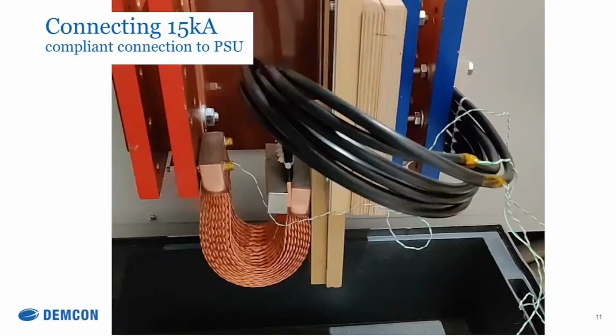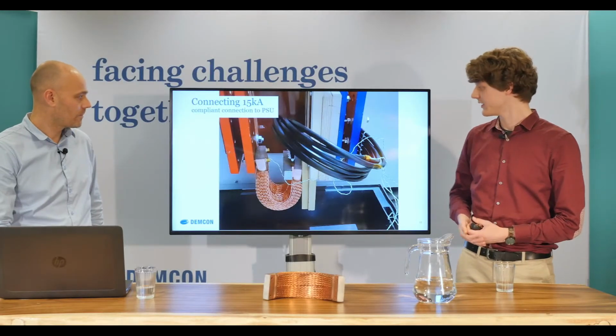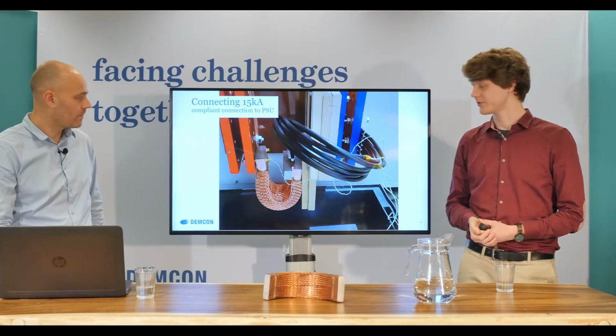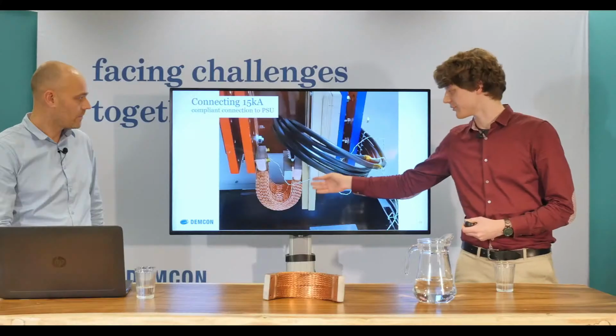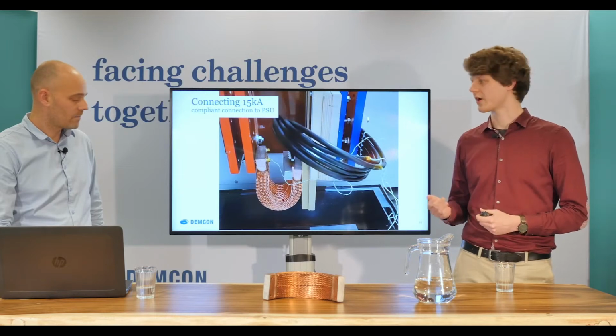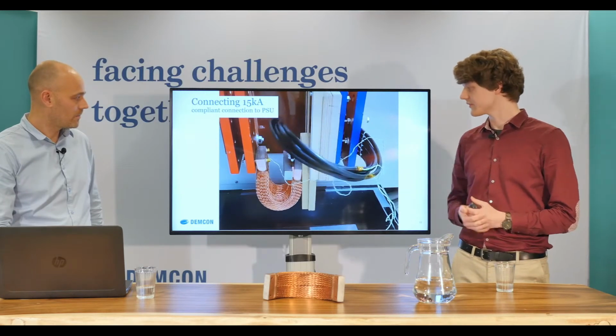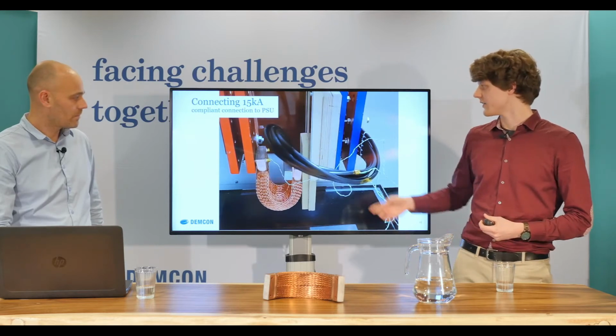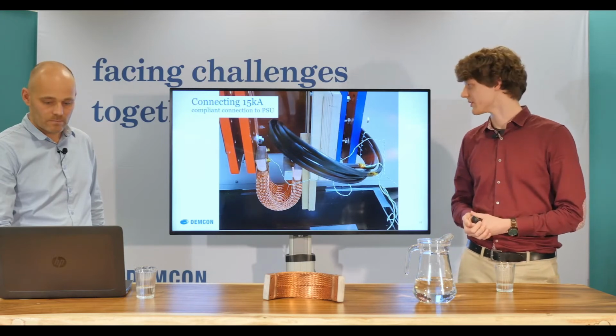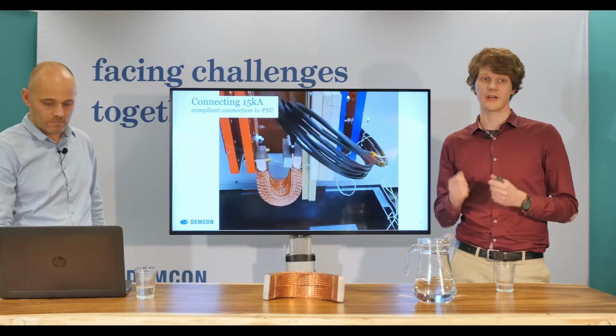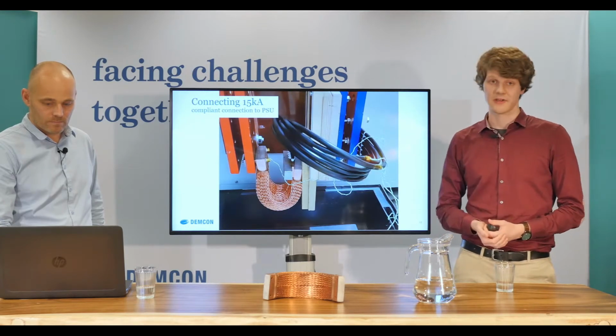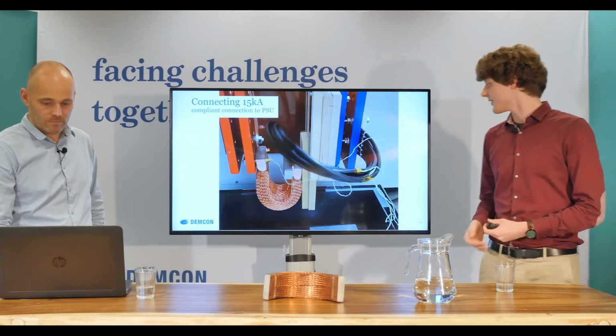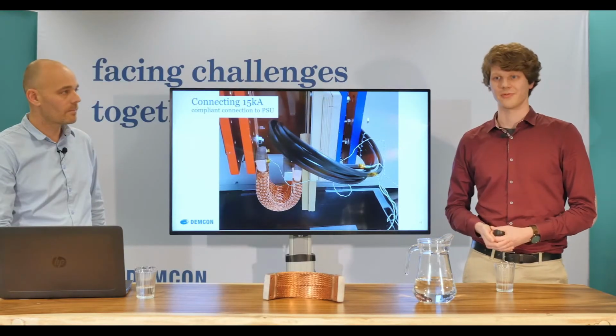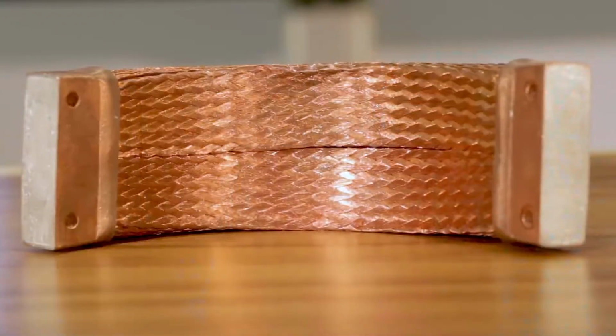So over here is a picture and a movie of a test we did with braided copper. So you can see the connections of the power supply linked together with the braided copper and some remaining copper cables. Now, this test was to confirm that this braided copper piece remains flexible even under a high current. So what you can see in the test is that we move it without the current, then we apply the large current on it, and you can see the black cables pinch together, which is the effect we're investigating. And fortunately, when we move it again once the current is applied, the braided copper stays flexible, and therefore the test is successful. And a little bit of a fun fact, we are measuring the temperatures on these black copper cables, and these heated up to about 100 degrees within 10 seconds. So the heat load is again very dangerous.